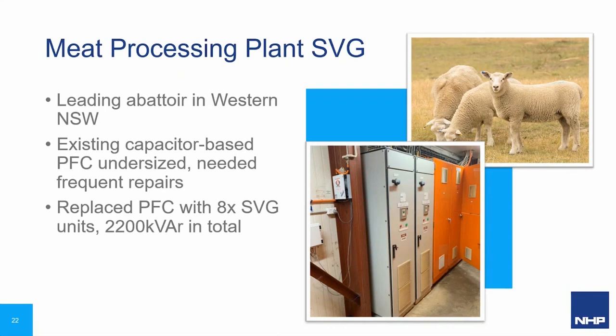After that, at that point, we had a clear vision of what sizes were required. Then it was a case of looking and discussing with the customer what problems they had in the past. Now, from the feedback we got from the customers and what we found during the audit and the servicing, they had a very poor history of component failures across items like contactors, and they experienced a lot of premature depletion on their existing cap-based systems due not only to heat, harmonics, and lack of maintenance.